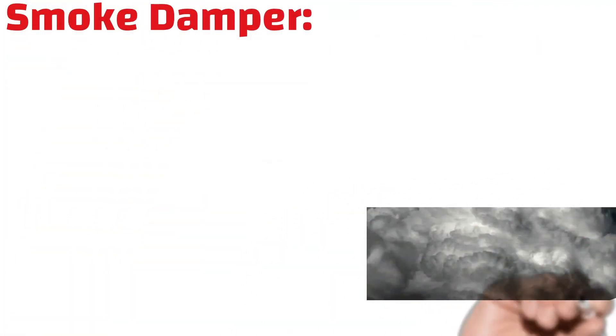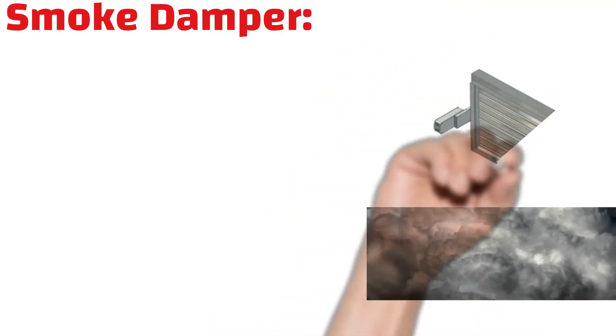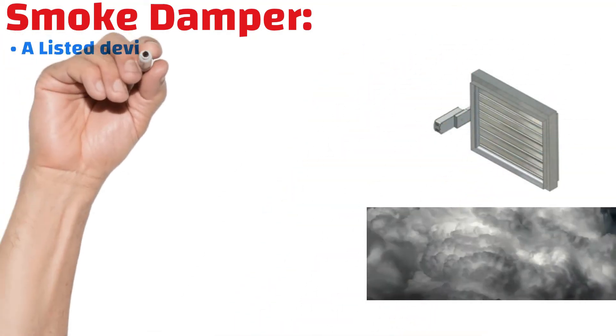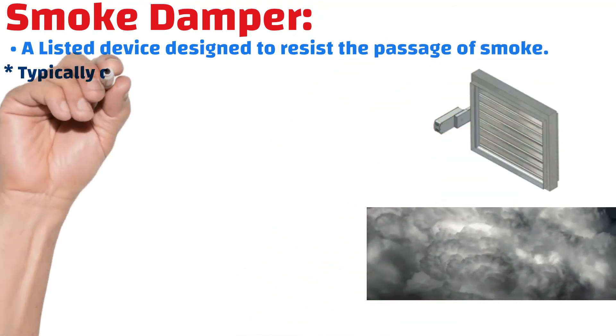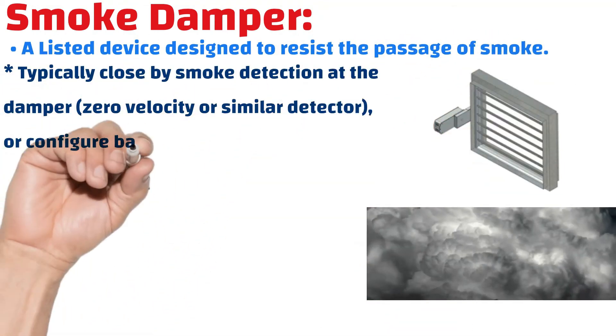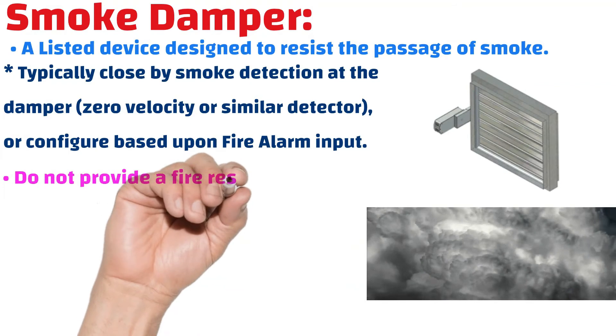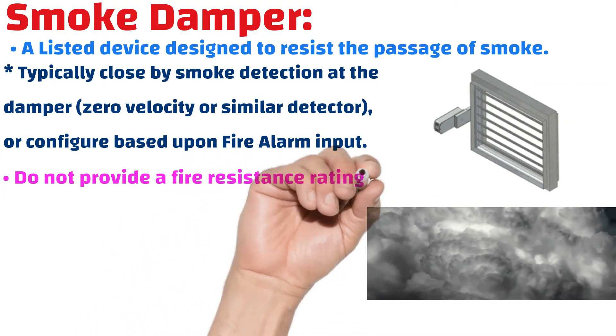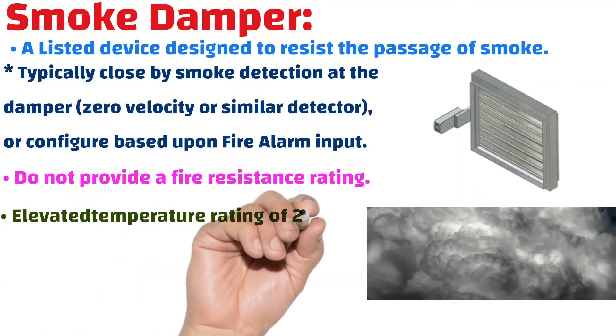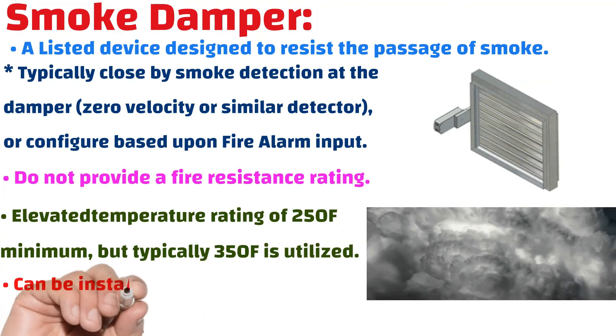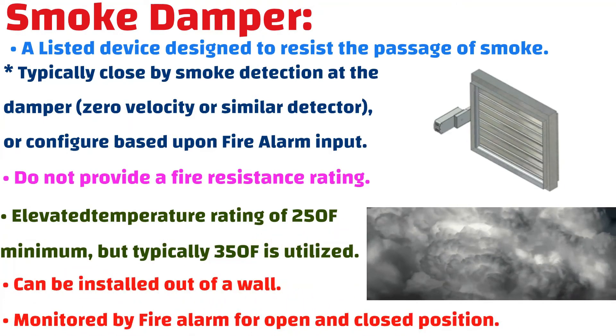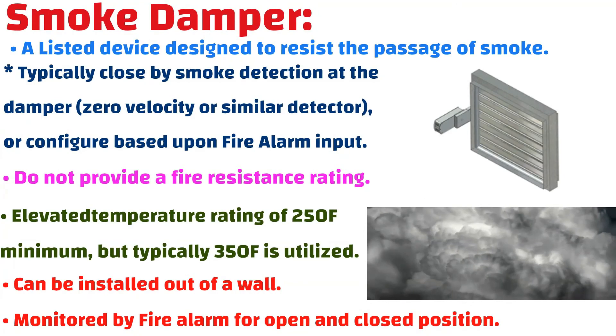What is a smoke damper? It is a listed device designed to resist the passage of smoke, typically closed by smoke detection at the damper or configured based upon fire alarm input. It does not provide a fire resistance rating. The elevated temperature rating is 250 degrees Fahrenheit minimum, but typically 350 degrees Fahrenheit is utilized. It can be installed out of a wall and is monitored by a fire alarm for open and closed position.